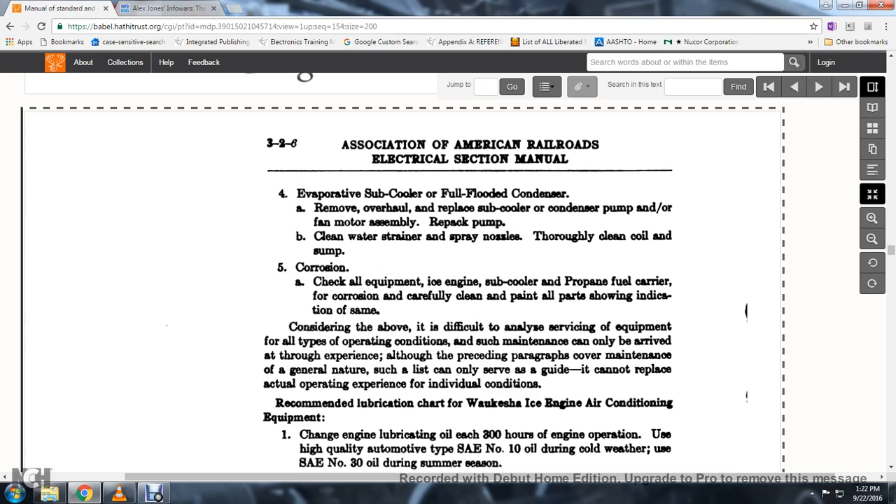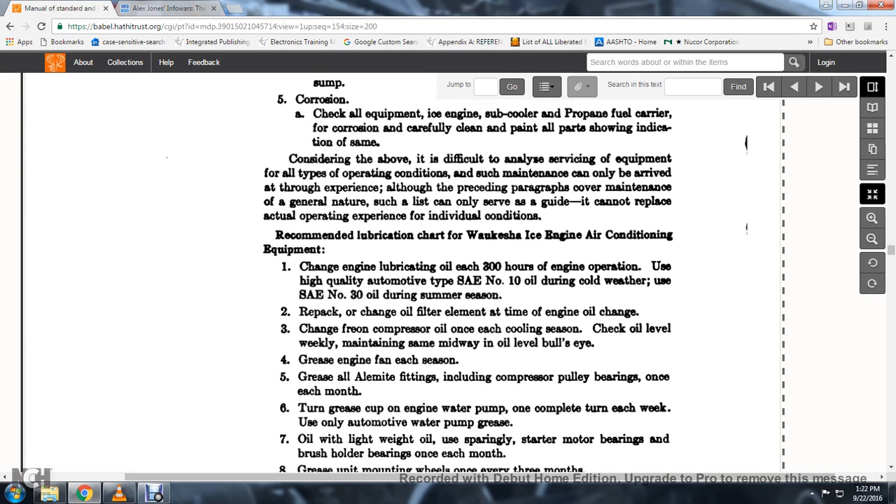Evaporative sub-cooler and fully-flooded condenser: remove, overhaul, and replace the subcooler, condenser pump, and fan motor assembly; repack the pump. Clean water strainer, spray nozzles, and thoroughly clean the coil. Check all equipment for ice engine subcooler and propane fuel carrier for corrosion; carefully clean and paint all parts showing indication of corrosion.